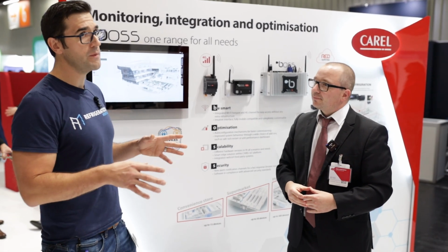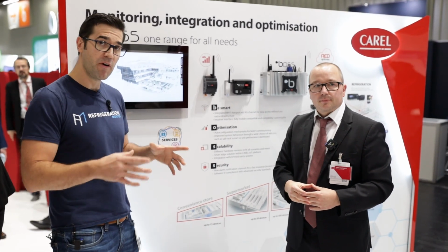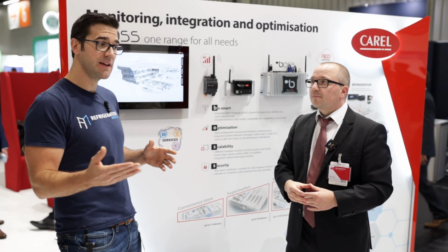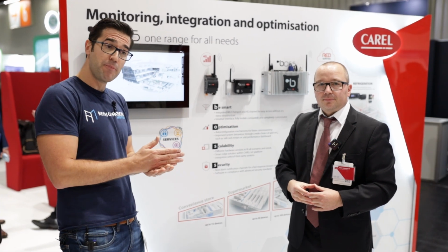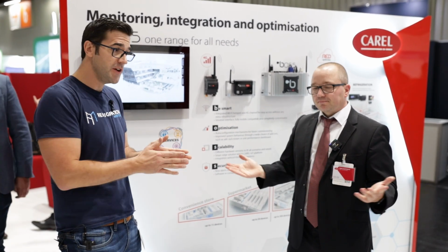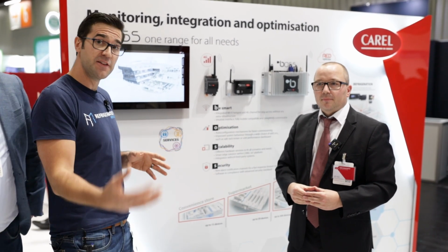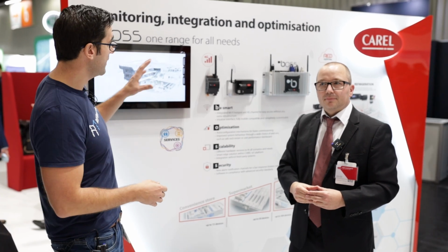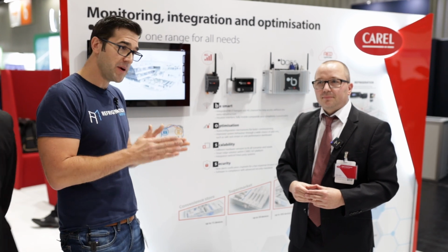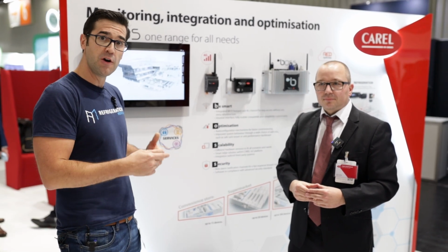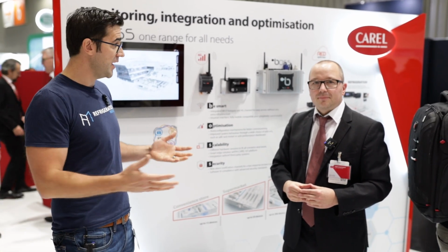Yeah, and that's so important, because with electronics, if you do not set it up or fine tune it properly, you could run into issues like that. Like Timo's saying, if that electronic expansion valve closes in the evaporator, it shuts off the circuit. So you got no mass flow, and that's going to affect other parts of the system. When you have a communication device like this that talks to it and says, okay, well, we'll close down a little bit, but not close fully, so we keep the flow going and move that transfer of heat, right?